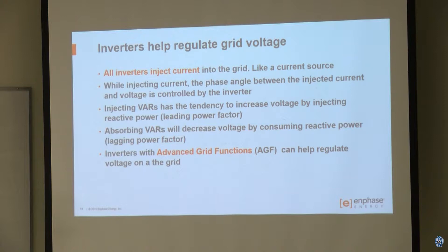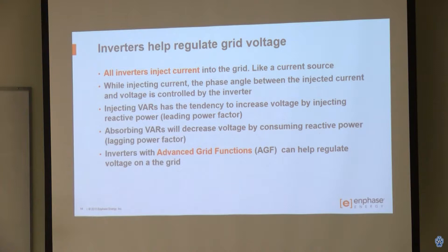How can inverters help regulate grid voltage? All the inverters inject current into the grid — they act like a current source, tracking the voltage and injecting current. But I can change the phase angle of that injected current relative to the voltage — I can advance or retard it relative to the peak. By doing that, I can either inject VARs or absorb VARs. When I'm injecting VARs I tend to raise the voltage; when I'm absorbing VARs I tend to decrease it. Inverters with advanced grid functions use this compensation scheme to help regulate the voltage on the grid.